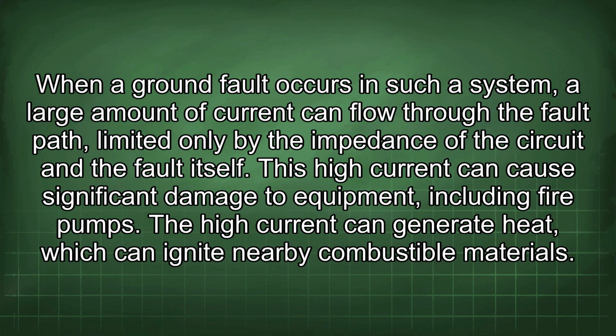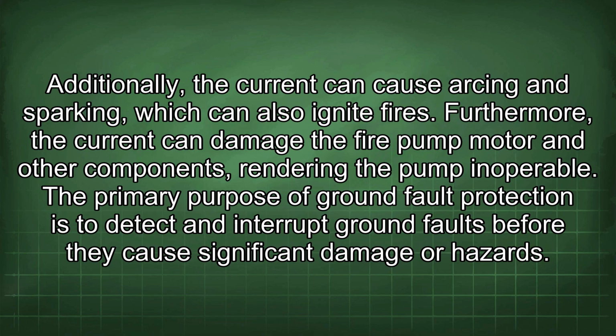When a ground fault occurs in such a system, a large amount of current can flow through the fault path, limited only by the impedance of the circuit and the fault itself. This high current can cause significant damage to equipment, including fire pumps. The high current can generate heat, which can ignite nearby combustible materials. Additionally, the current can cause arcing and sparking, which can also ignite fires. Furthermore, the current can damage the fire pump motor and other components, rendering the pump inoperable.